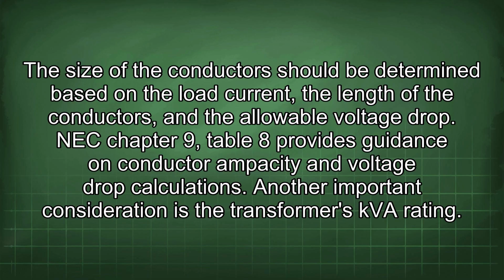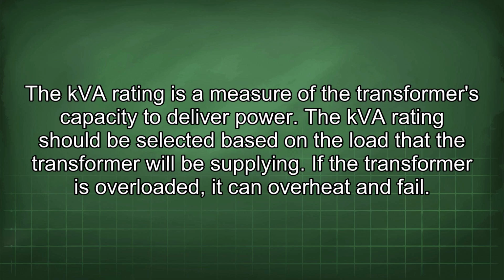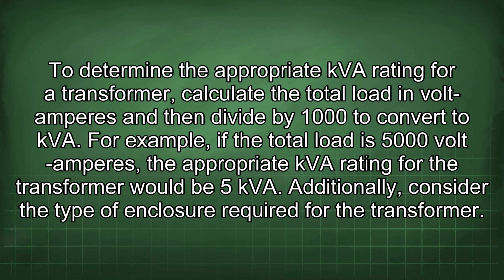Another important consideration is the transformer's kVA rating. The kVA rating is a measure of the transformer's capacity to deliver power. The kVA rating should be selected based on the load that the transformer will be supplying. If the transformer is overloaded, it can overheat and fail. To determine the appropriate kVA rating for a transformer, calculate the total load in volt amperes and then divide by 1000 to convert to kVA. For example, if the total load is 5000 volt amperes, the appropriate kVA rating for the transformer would be 5 kVA.